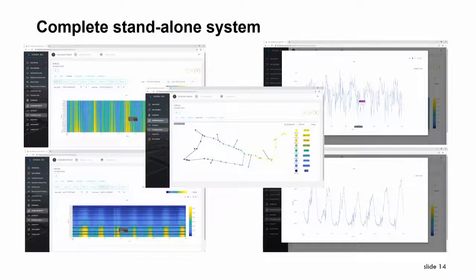So especially the voltage profile is reasonably easy to estimate. As you increase the number of measurement points available, the second operational parameter that converges is the flows towards the upstream network, which is mother math at her kindest, I'd say. These are the two parameters we're most worried about in terms of limiting network capacity: the voltages further down in the network, and the flows that tend to be most extreme towards the infeed. Exactly these two parameters are the ones that get more precise earliest.